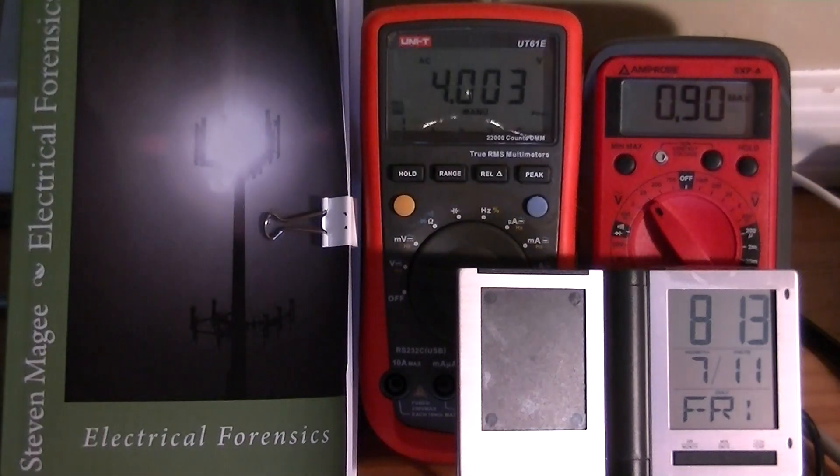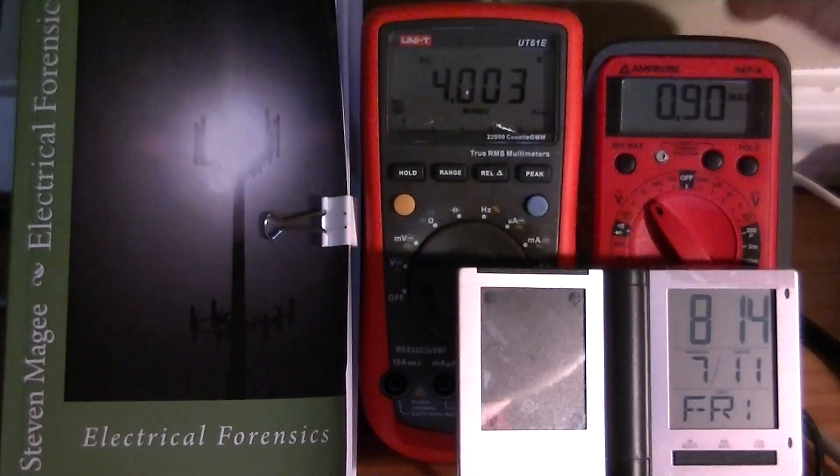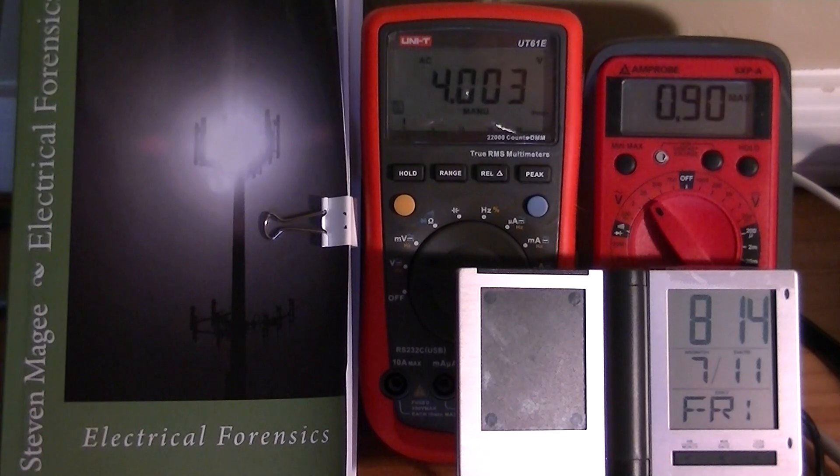This is an Amprobe AXP-A and you can see that it's actually indicating a value of 0.9 volts AC maximum. We can switch to the minimum and you see that we almost went down to zero — we got 0.05 volts AC for the low. Obviously when dealing with stray voltage you're interested in the high, so that 0.9 is pretty typical for the weather pattern that has been occurring over the last couple of days.